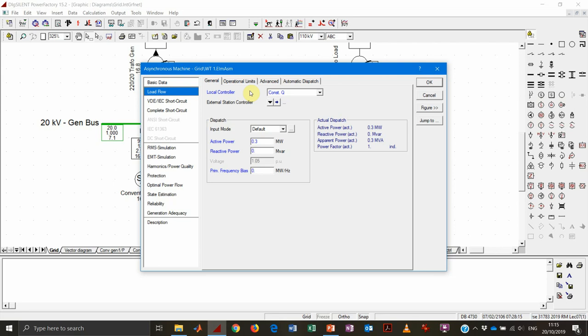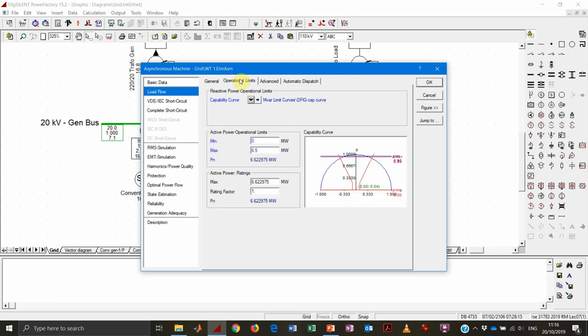For this type of machine, as for any other generator, we can provide dispatch values in terms of active and reactive power. We can specify whether voltage or reactive power should be set. We can also characterize a capability curve for this machine — which is of course much narrower compared to a conventional synchronous machine. Still, it can provide a certain amount of reactive power when there is active power production, and typically the larger the active power, the larger the reactive power capability. This capability is adjusted to fulfill the grid code requirements of each country.